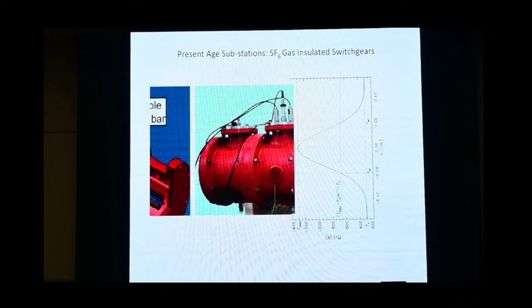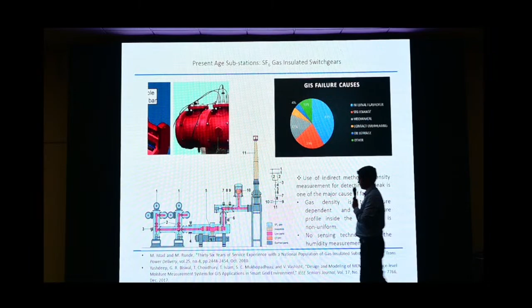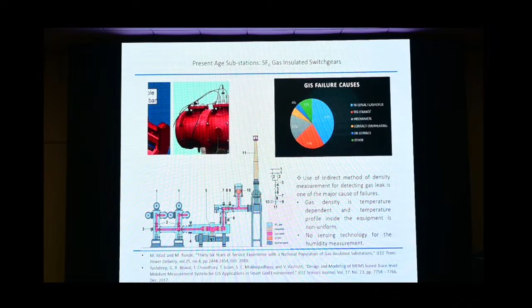This distribution is basically a temperature profile. What happened here is this vessel has live conductors. These pink colors you see are the residual SF6 gas, sulfur hexafluoride, used as the insulation medium instead of air. Why? Because we get better arc quenching capability and other distinct thermal advantages.